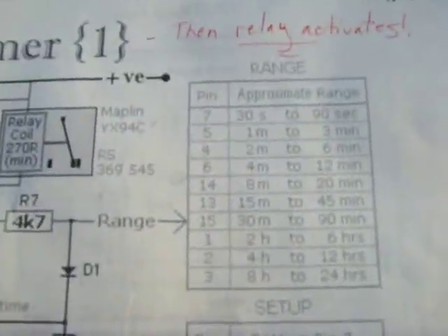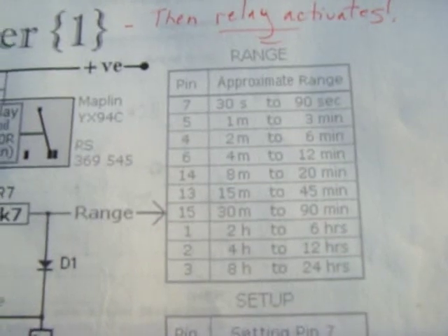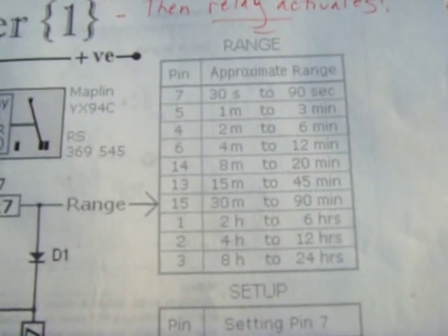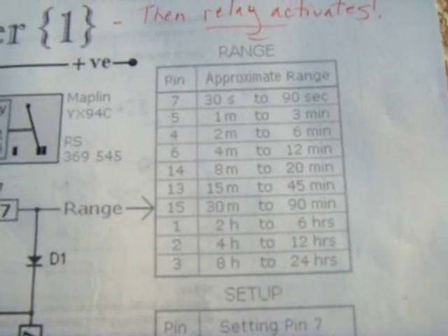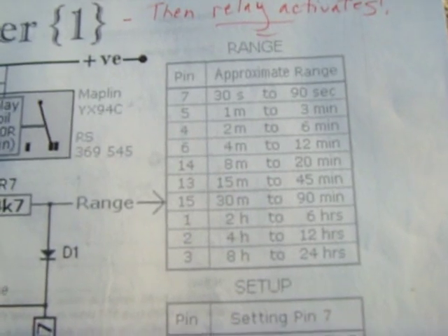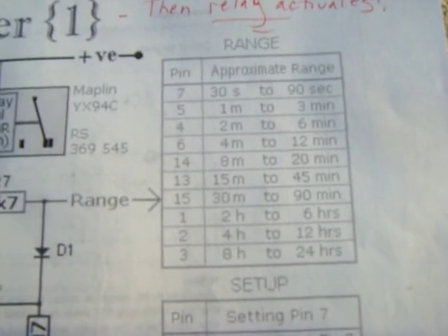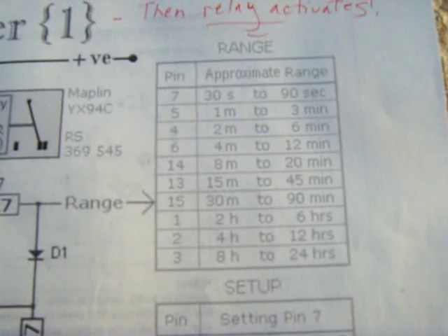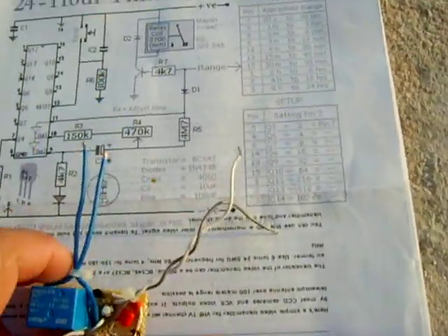If you look at this chart, you'll see all the time frames. Pin 15 is 30 minutes to 90 minutes, pin 5 is 1 minute to 3 minutes. That's where that white wire would connect. So if you want 10 minutes, you use pin 6. But you also have to set this potentiometer right here.